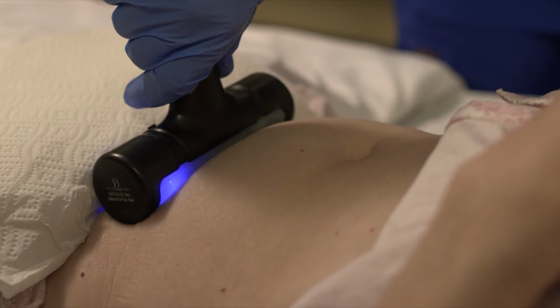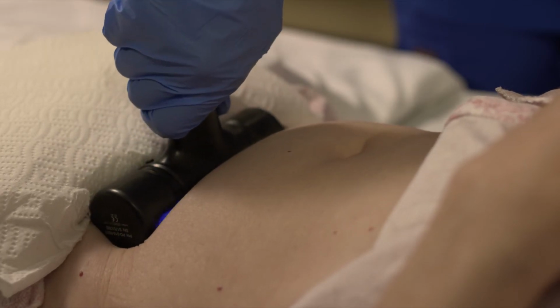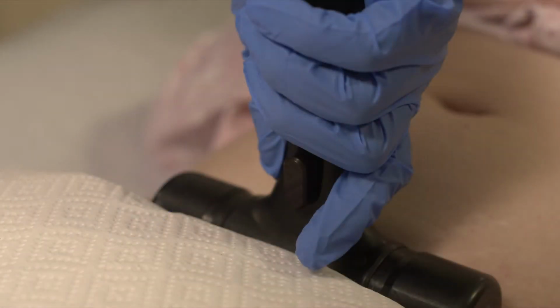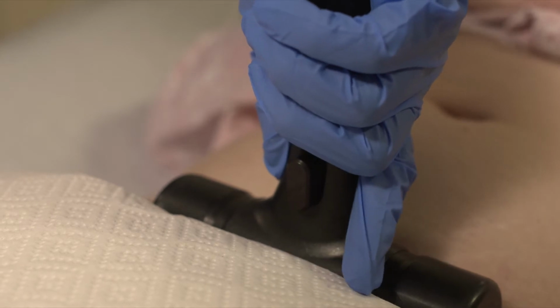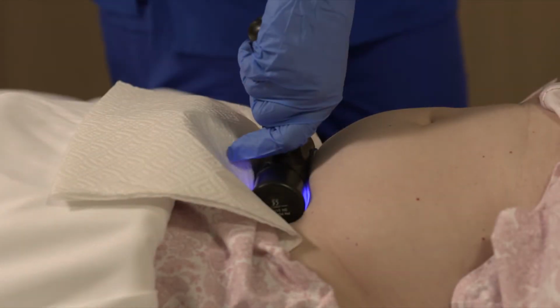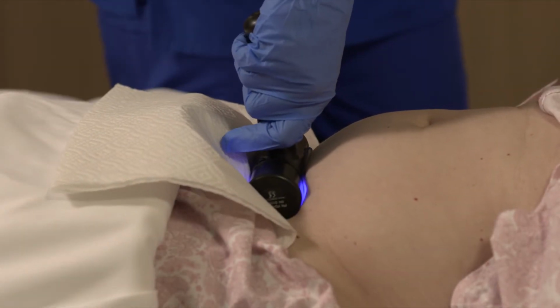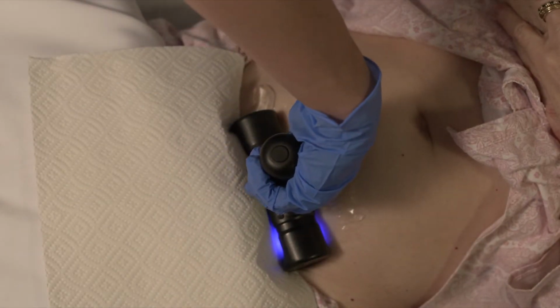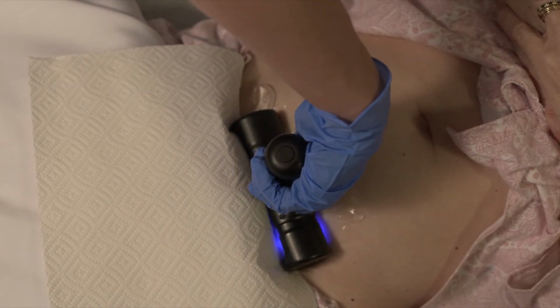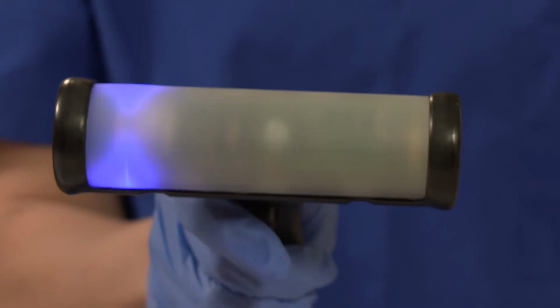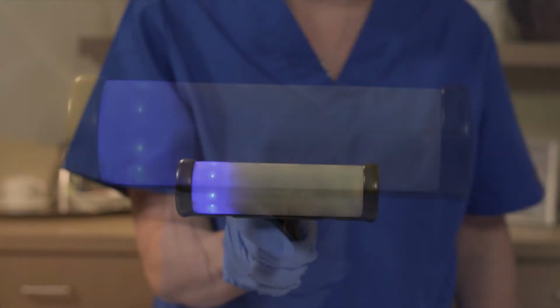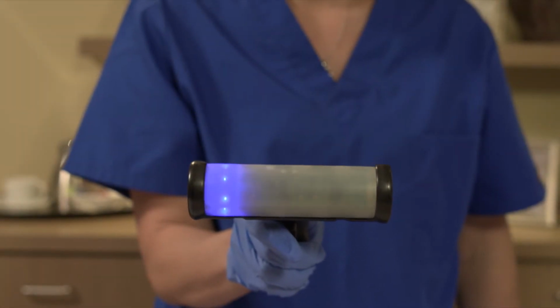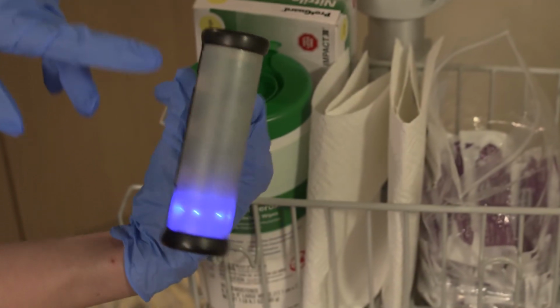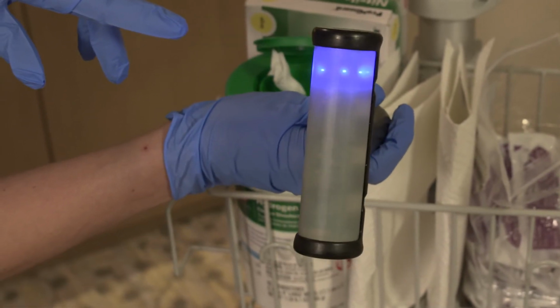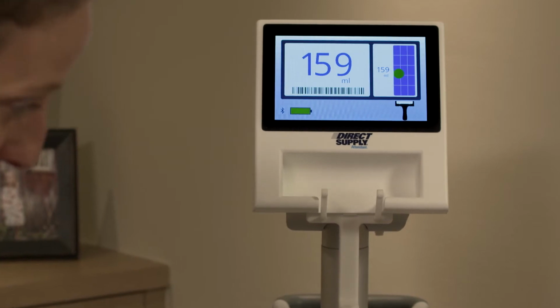Then, press the scanner probe in the tissue until its window portion is no longer visible. Next, press and release the button to perform a scan. There is no need to move or aim the scanner probe. Hold the scanner probe steady during the scan for approximately 3 seconds. The 8 individual transducers will spin inside the scanner probe to automatically locate the bladder. You may see a small air bubble in the probe window. That is normal. The volume will be displayed on the console.